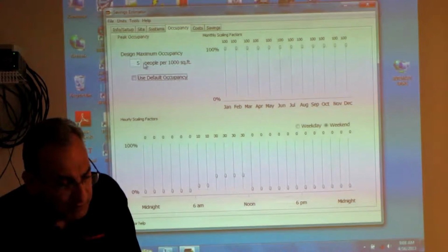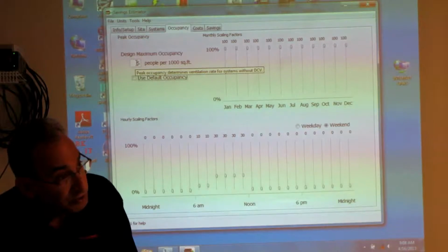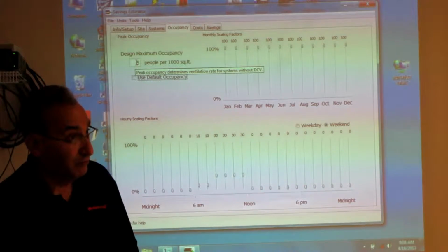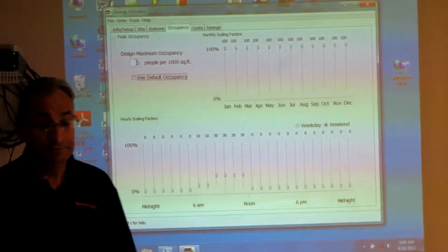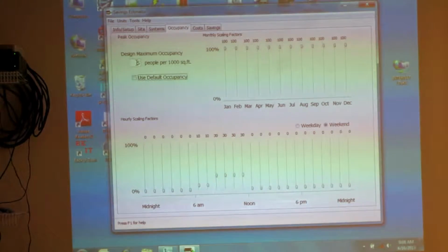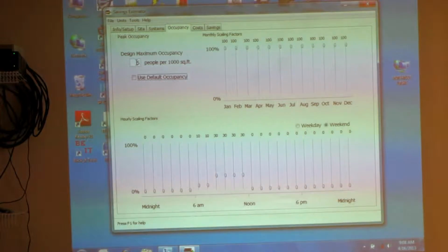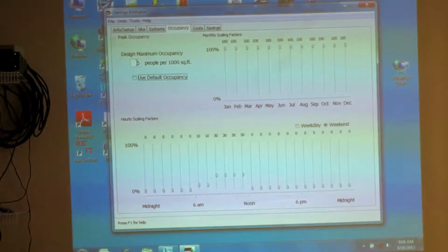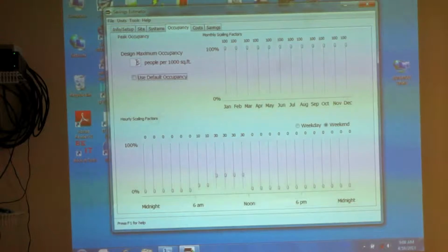And if you go by number of people, maybe you have more people in that. Of course, then your dampers are opening more fresh air. Now, if you have leakage, if I put in there like a 10% leakage of those dampers, all that savings goes away. I mean, just amazing. I thought I had done something wrong in the calculation. It's just the leakage is a killer.